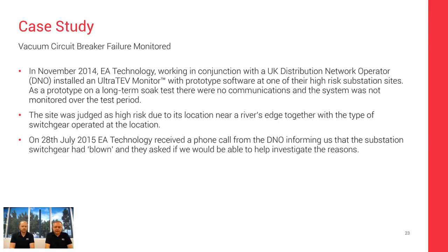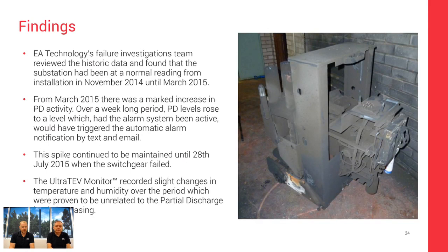It was a high risk, quite a critical switchboard. It was near a river. It's a particular type of switchgear that doesn't particularly like high humidity and has been known to discharge. So we installed the monitor in November 2014, and at the end of July 2015, we received a phone call that the substation had blown up, and could we investigate the reasons? So the substation blows up, and people say, oh, we've got a monitor on that. Possibly you want to do it slightly differently.